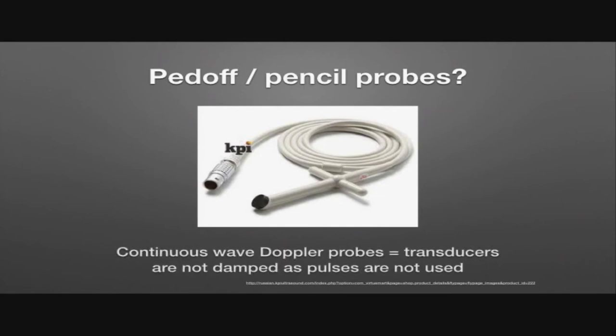What about Pedoff, or pencil probes — what damping material is contained in them? This is a bit of a trick question, because these are continuous wave Doppler probes. There are no pulses used in these probes, and therefore no significant damping material is required.